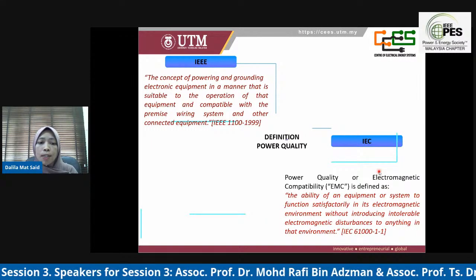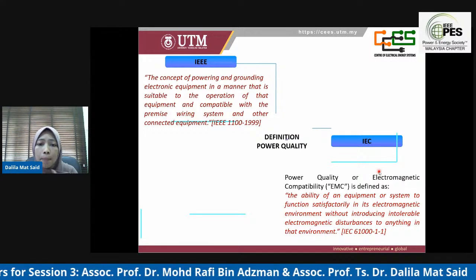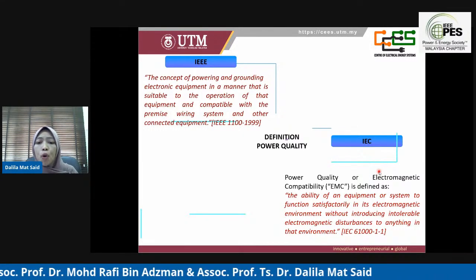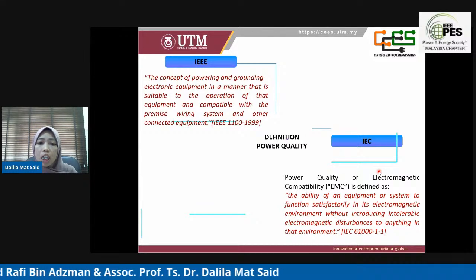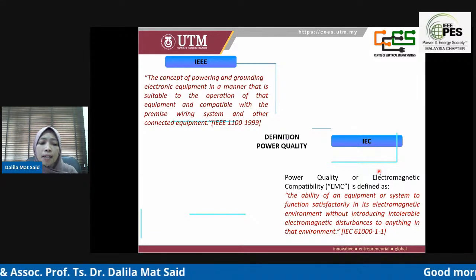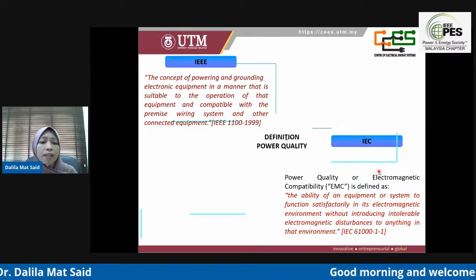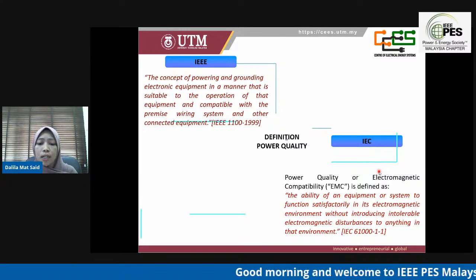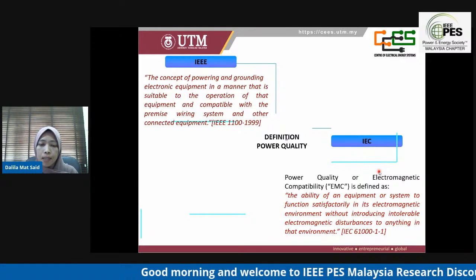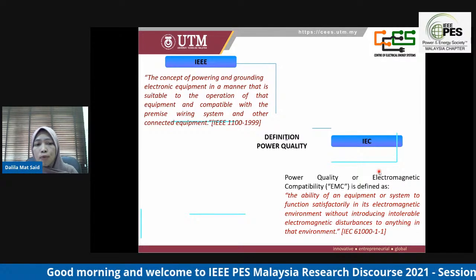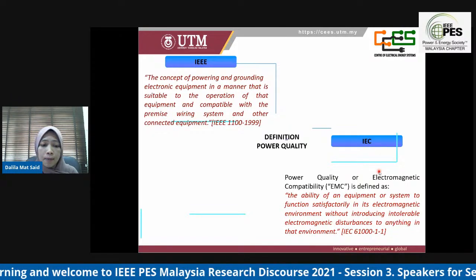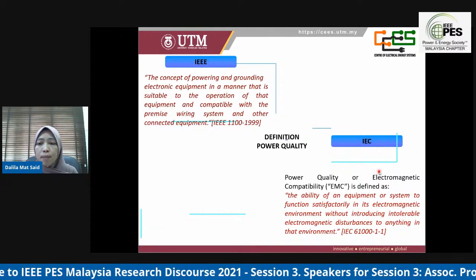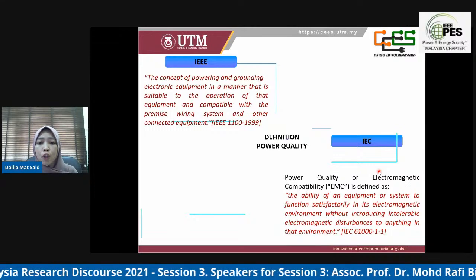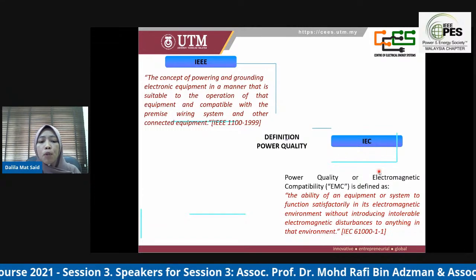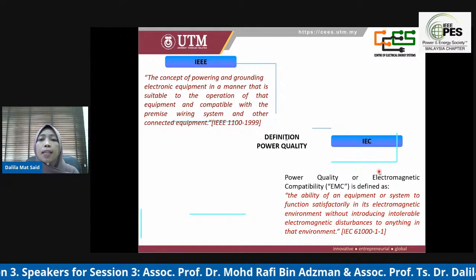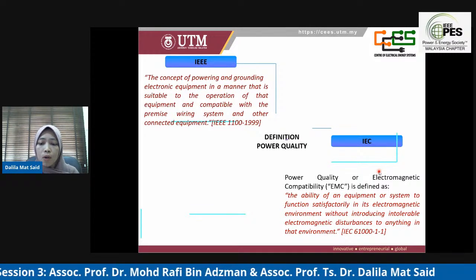Or, the best measure of power quality is the ability of electrical equipment to operate in a satisfactory manner, given proper care and maintenance, and without adversely affecting the operation of other electrical equipment connected to the system. In IEC, there are two sides of the EMC equation: the source equipment whose emission must be limited, and the equipment that needs to have sufficient immunity to this disturbance in the environment within which it operates.